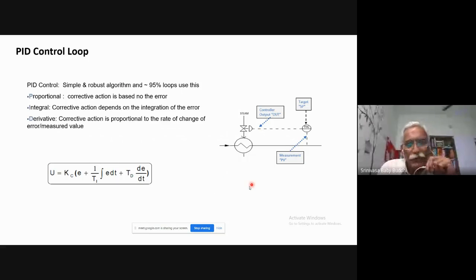Typically a control loop consists of, for example, a heat exchanger where steam is used to heat the process stream. You have a temperature measurement of the hot water coming out of the heat exchanger. This measurement is made available to the temperature indicating controller, where you feed a set point. Based on the measurement and the target set point, whatever the error is, the controller algorithm, typically the PID controller, calculates the output, and the output signal goes to the field and manipulates the control valve, either increasing or decreasing the steam based on the current process value. So this is a typical control loop.